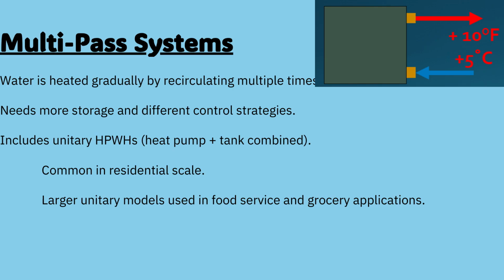On the other hand, multi-pass systems work by circulating water through the heat pump multiple times, adding a smaller temperature lift with each pass. These designs need more storage and more careful controls. A subcategory of multi-pass systems is the unitary heat pump water heater, where the heat pump and storage tank are combined into a single unit. These are common in residential applications, but larger versions are available for food service and grocery facilities. In short, while both technologies have their place, single-pass systems often deliver the best efficiency, the least storage requirement, and the most reliable performance in commercial and multifamily projects.